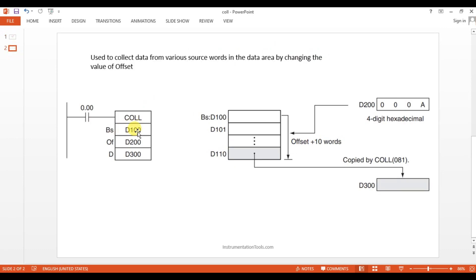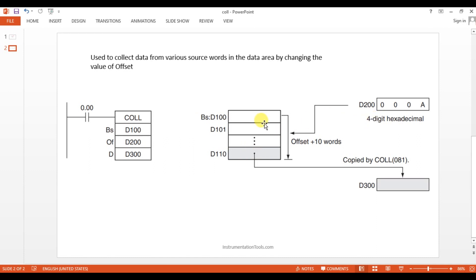Here they are having D100, D200, D300. Now we have to bother about this offset. Look at this. Here the offset is 10. What this instruction is going to do is from source address, it will calculate the address where we are going to copy. It depends upon the offset. D source is 100. From that offset, you have to add 10, so it is D110. In D110, it will copy the data and put it in the destination. This is what we call it as data collect instruction.